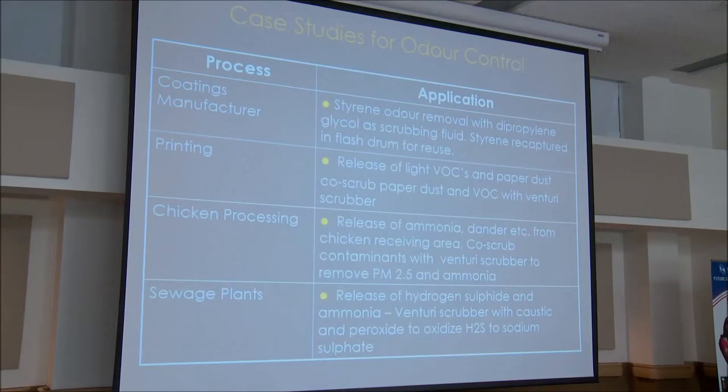For a coatings manufacturer, we were involved with a project where we used dipropylene glycol to scrub styrene from the process. This acts as a solvent to remove the styrene from the airstream, which was then recaptured in flash drums for reuse — sprayed into a tank with no headspace where the styrene was released and condensed for reuse in the process. In printing, the release of light VOCs and fine paper dust can be co-scrubbed with a Venturi wet scrubber.